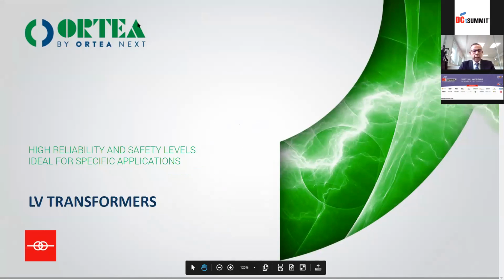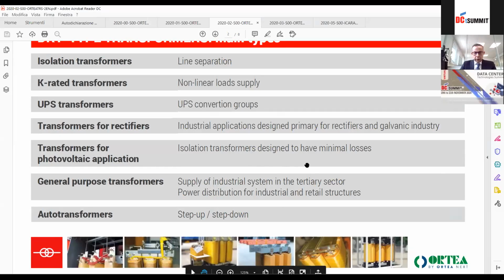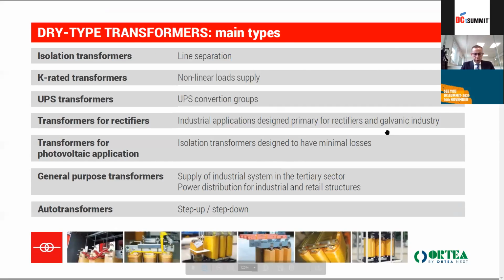So isolation transformers are mostly very, oh, sorry, here. Okay, they are dry type transformers. So we do produce them with resin impregnation. So they are no cast resin. Mostly used for UPSs because we have a very good relationship with many UPS producers, and we deliver them a lot of isolation transformers for their UPS. There are also transformers for other applications like solar system, photovoltaic, rectifiers, general purposes, step up, step down, auto transformers. We do have also some other application like reactors for medium voltage, etc.